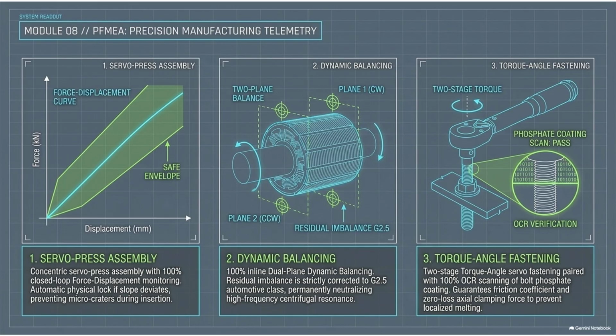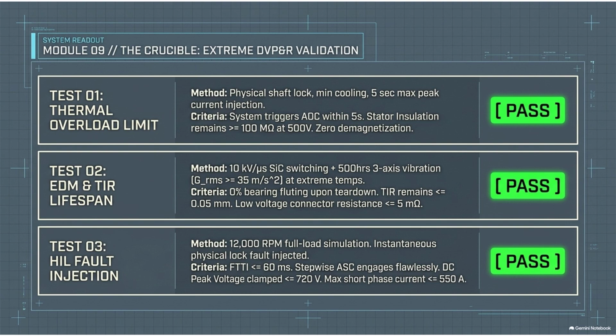They pump 500 volts of high-pressure DC current through the wiring. The insulation resistance must still measure 100 megaohms or higher. Megaohms, meaning it still perfectly resists the electricity. Yes. It proves that the polymer insulation did not melt, warp, or degrade even a fraction of a millimeter. Furthermore, they measure the permanent magnets on the rotor. Extreme heat and massive conflicting magnetic fields can permanently demagnetize a magnet. The test proves that the magnet survived the inferno completely unscathed. It has to survive a literal meltdown scenario without a scratch.